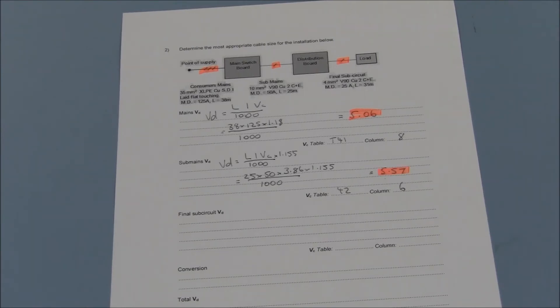Likewise for the single phase sub main, not neglecting to multiply the value of VC by 1.155. This gives us a voltage drop of 5.57 volts. Table 42 column 6 is the reference for this part.